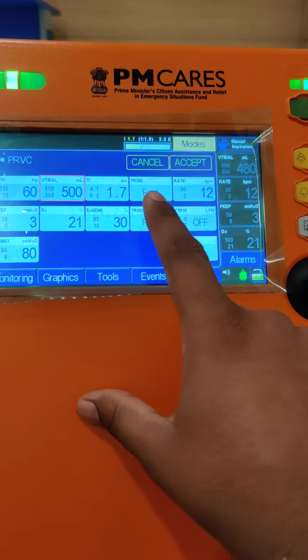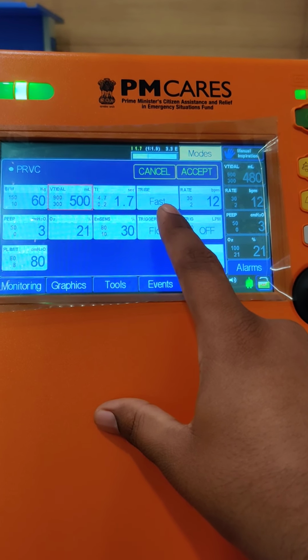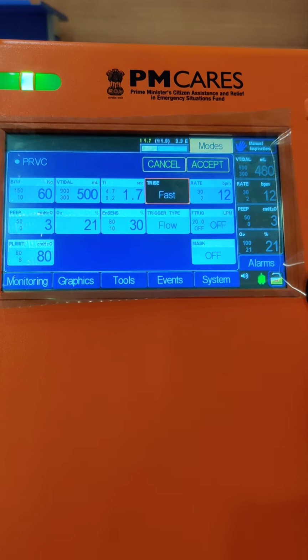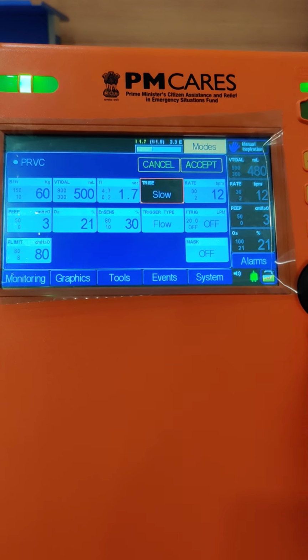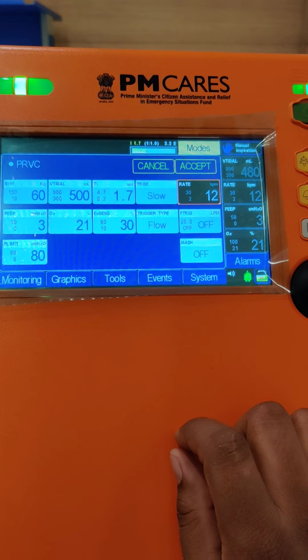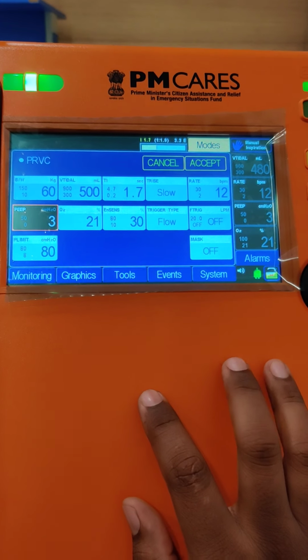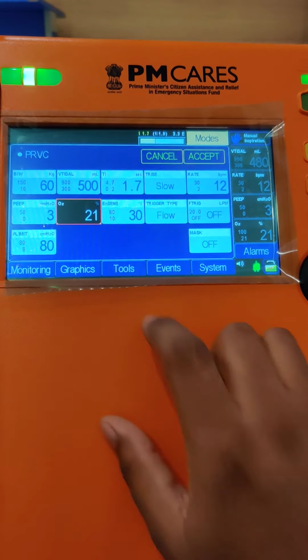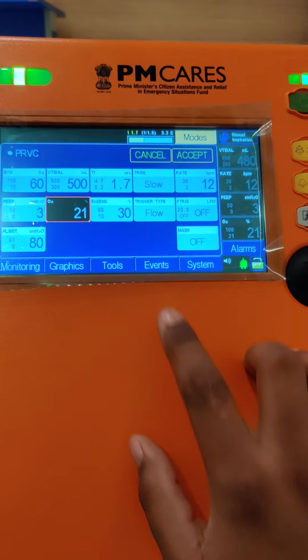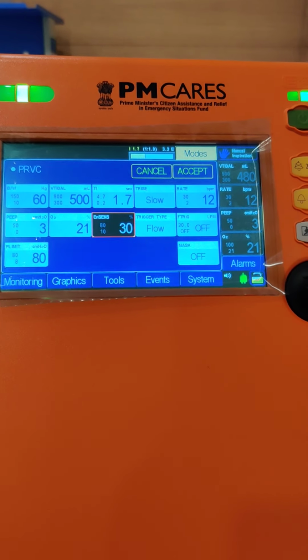You can set the inspiratory time in this. You can set the rise time of the flow, that is fast, medium or slow, depending on the patient's requirement. This is the rate, that is the frequency. This is the positive end expiratory pressure, PEEP. O2 you can set from 21 to 100%. This is the expiratory sensitivity.